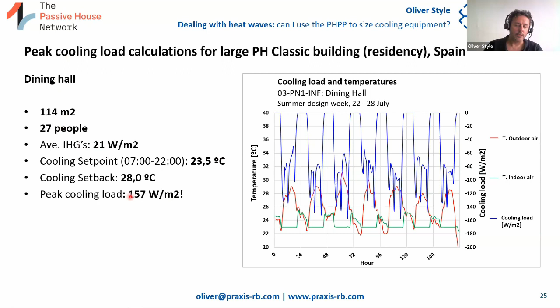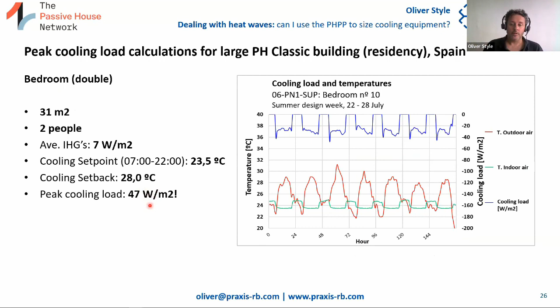So if we follow the same example of this elderly people's residency, a double bedroom with 2 people in 31 square meters, average heat gains of 7 watts per square meter, then we've got a peak cooling load of 47 watts per square meter. That's kind of where we were on average that we saw in the previous graph across all those projects, which would be more of a residential setting.